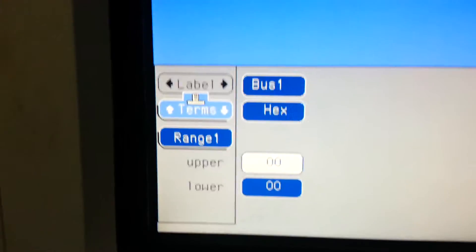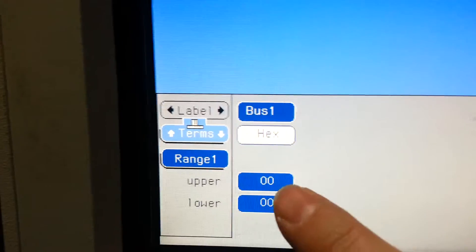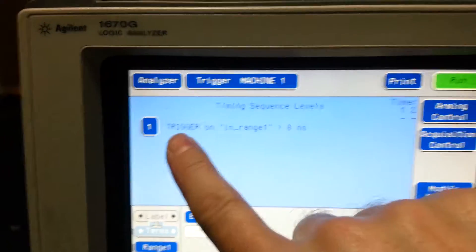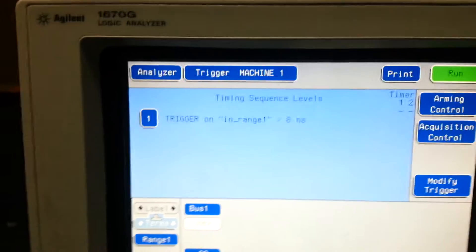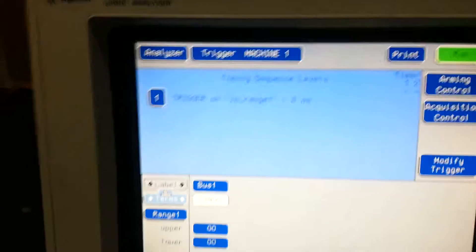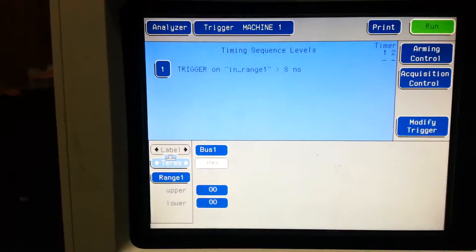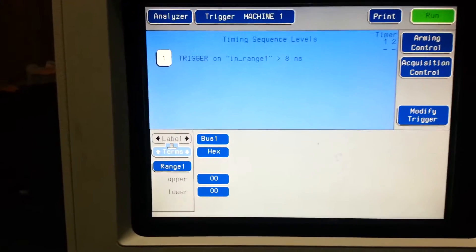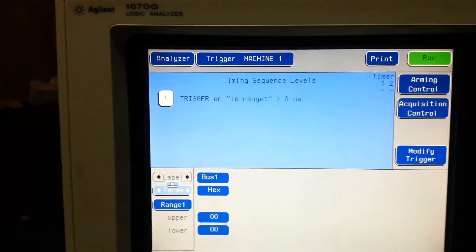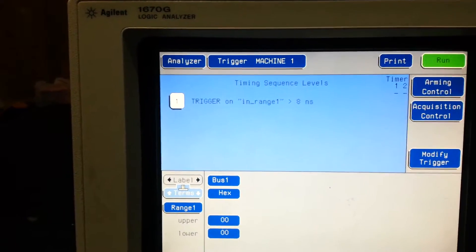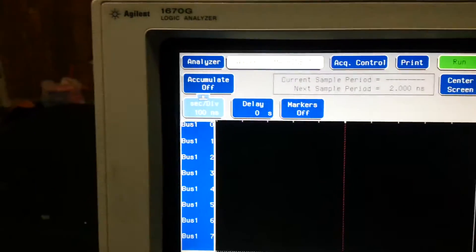Capture that. So we're gonna say our upper and lower range is zero, so our trigger will kick off after we've been in range one for at least 8 nanoseconds. Let's go to waveform. Let's go to acquisition.